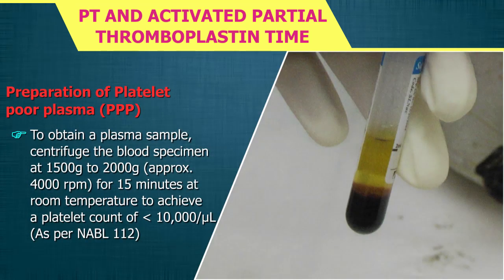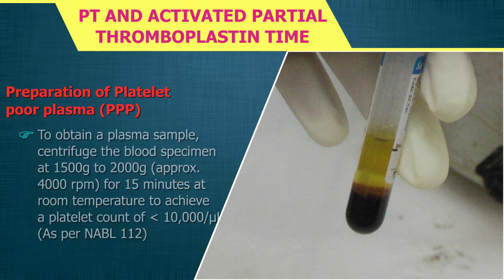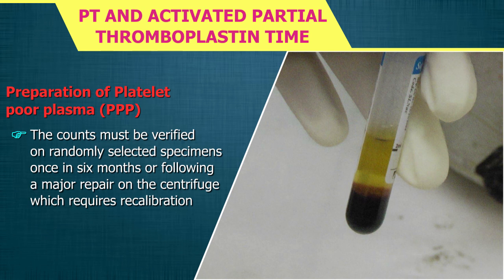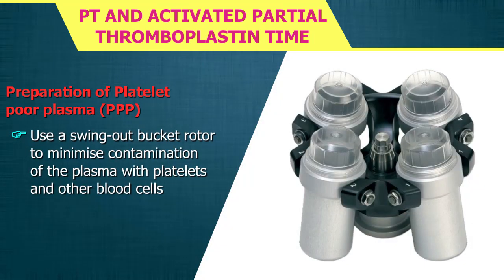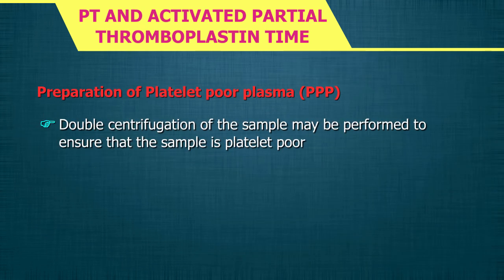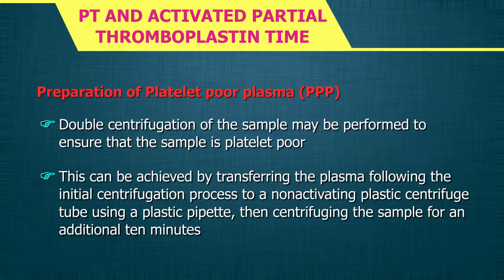To prepare platelet poor plasma (PPP), centrifuge the blood specimen at 1500g to 2000g (approximately 4000 rpm) for 15 minutes at room temperature to achieve a platelet count of less than 10,000 per microlitre, as per NABL standard 112. Counts must be verified on randomly selected specimens once every 6 months or following major centrifuge repair requiring recalibration. Use a swing-out bucket rotor to minimize contamination of plasma with platelets and other blood cells. Double centrifugation may be performed.